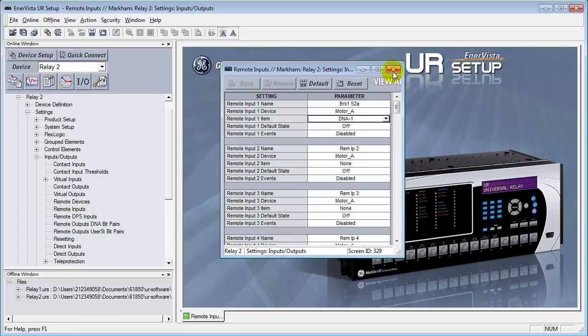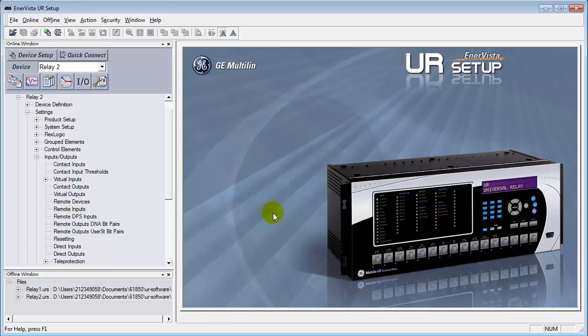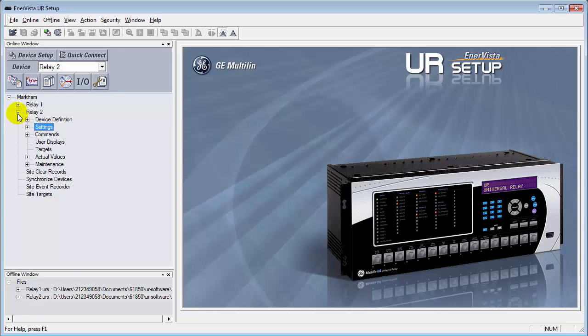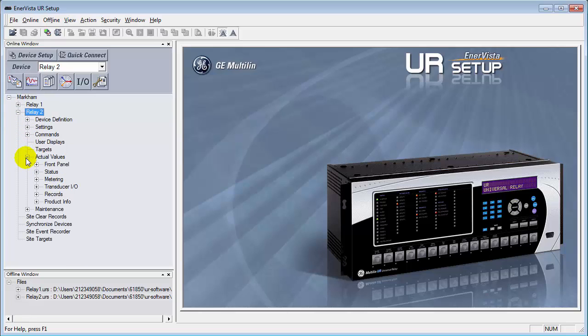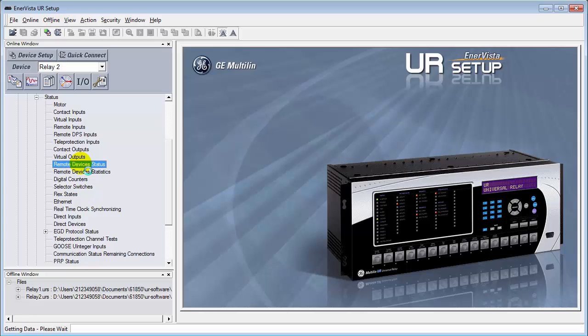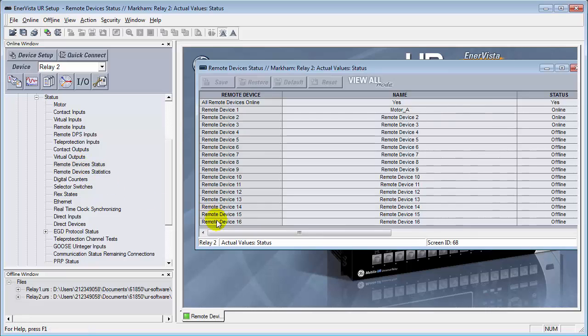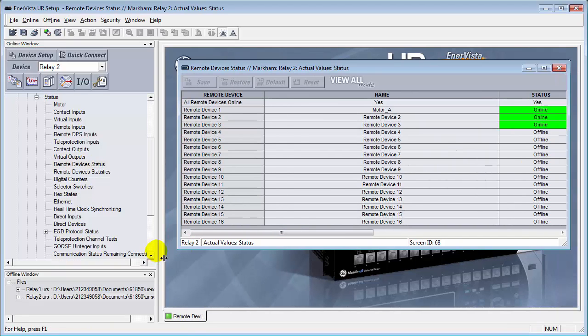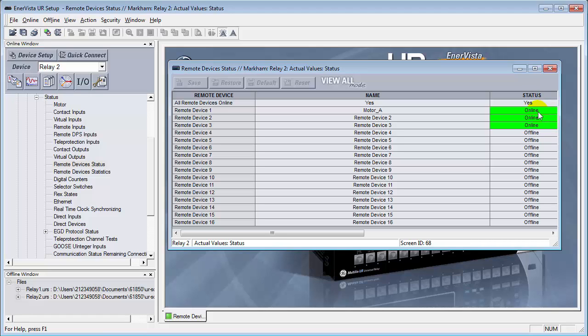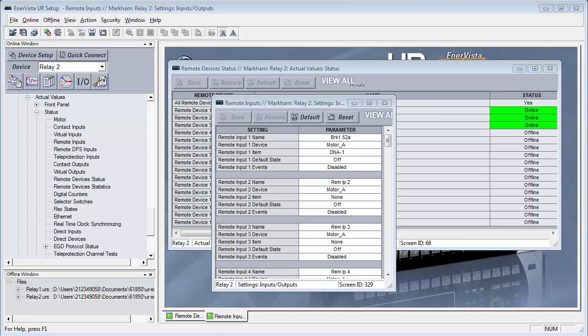Alright, now we'll close this. Let's confirm that we actually have our goose messages going across. On relay number two, we're going to open this up. And we're going to go down to the actual values section. And we're going to verify the status of our goose communications. The very first thing I normally check for is go to the remote devices status. This will tell us whether we're actually communicating with the other relay or not. Here it says, all remote devices online. Here's our goose message. And it says, yes, we are online with it. If there was an error in any of the programming, this would not be online. It would be indicated as offline.